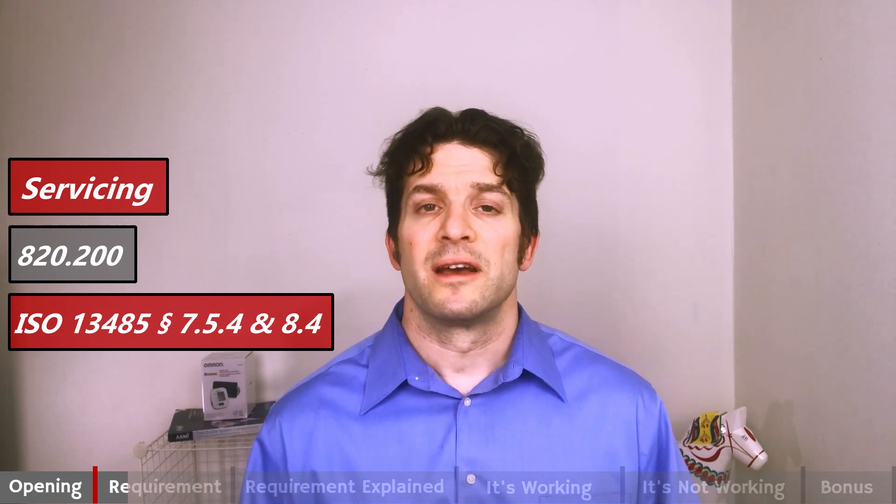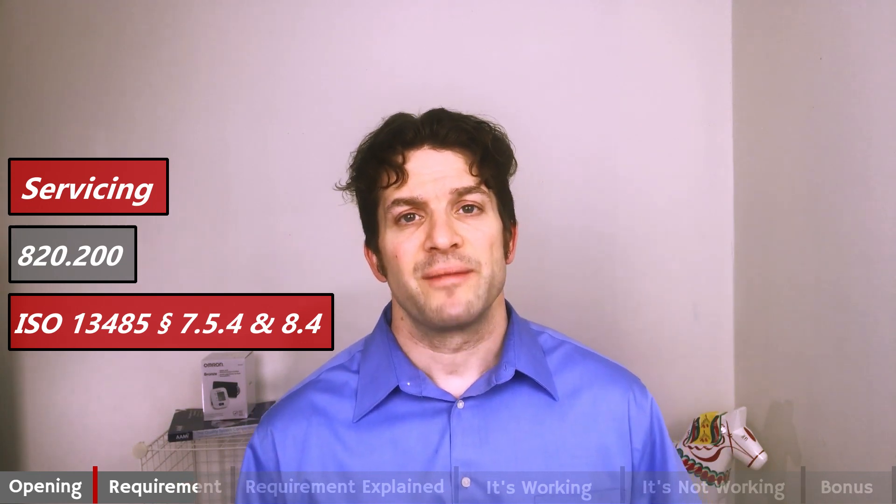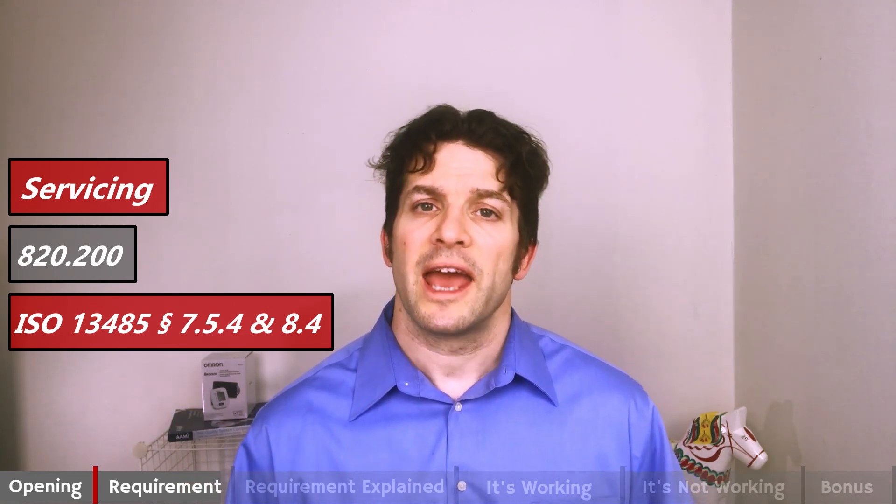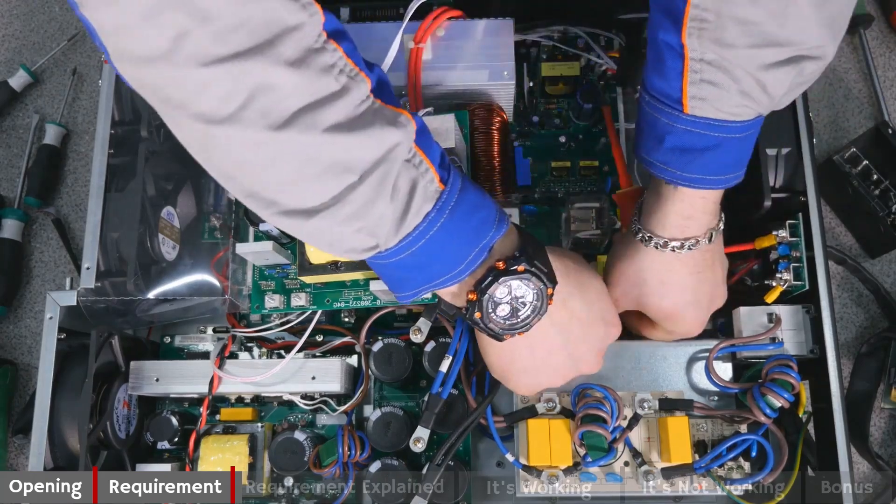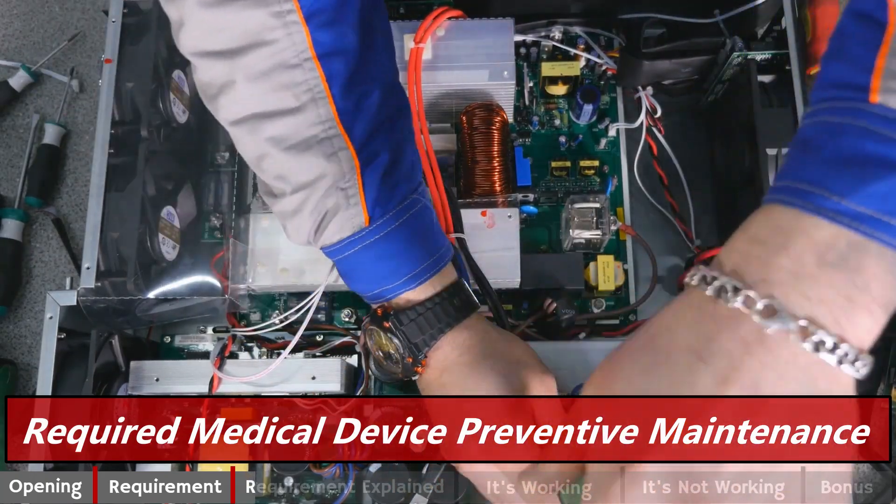Our requirement, servicing, comes directly from 820.200 and ISO 13485 sections 7.5.4 and 8.4. Servicing, in five words: required medical device preventative maintenance.